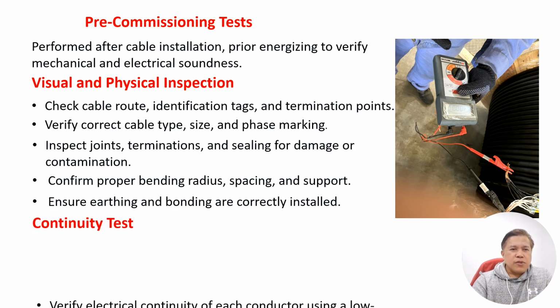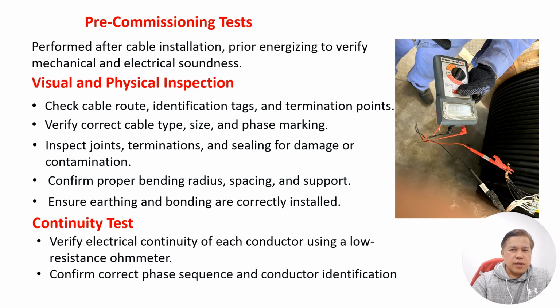Another one is the continuity test. You need to verify electrical continuity of each conductor using a low resistance ohmmeter, and confirm correct phase sequence and conductor identification. So, like what you are seeing here, this is our continuity test. You check the cable, then check the meter, continuity, everything is perfect, ready to install and ready to energize. All right.